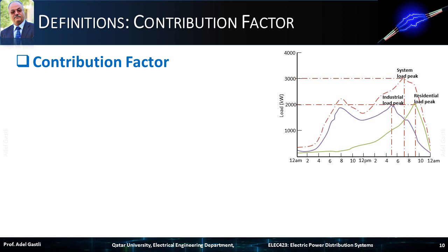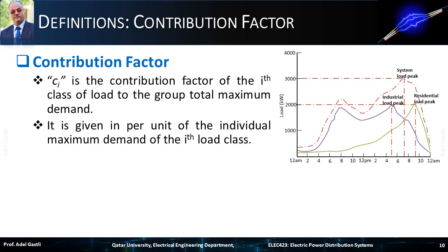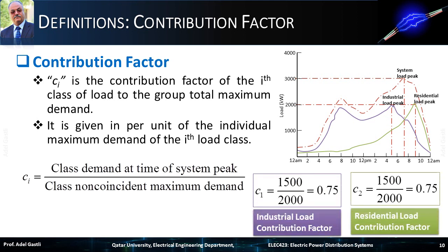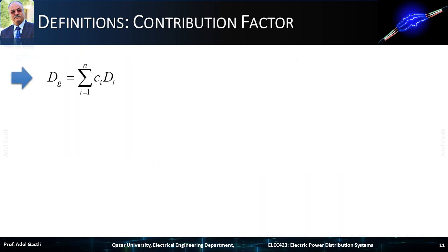Now let's define another factor: the contribution factor of an individual load i, denoted by Ci. Ci is the contribution factor of the ith load to the group maximum demand, given in per unit of the individual maximum demand of the ith load. It is the ratio of the class demand at time of system peak to the class non-coincident maximum demand. The total maximum non-coincident or diversified demand DG equals the sum of the contribution factor of load i times the maximum demand of load i, for i equals 1 to N. This is equivalent to writing the coincidence factor Fc as the ratio of the sum of the individual demand multiplied by its contribution factor, to the sum of the total maximum non-coincident demand.